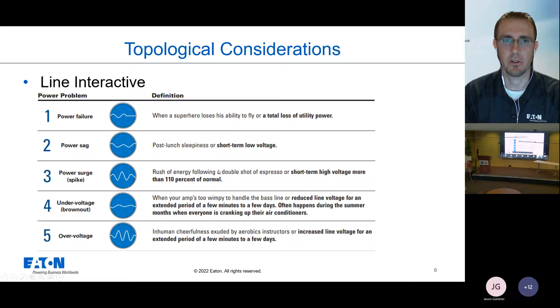With Line Interactive, you get protection from power failure, power sag, surge, under voltage, and over voltage. These are great for typical IDF environments where you may not need quite robust power. What does that mean? Protection from power outages plus minor power fluctuation correction. You want to use these where utility power is relatively clean—it saves money—and where the equipment is less sensitive to power disruptions.